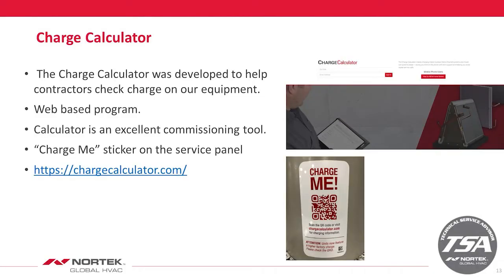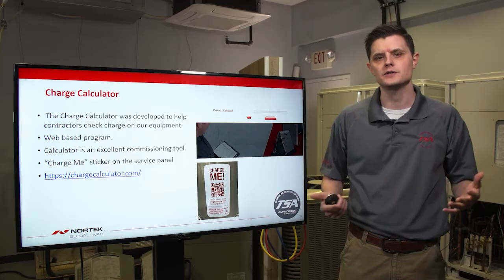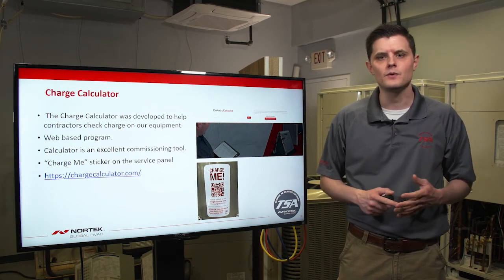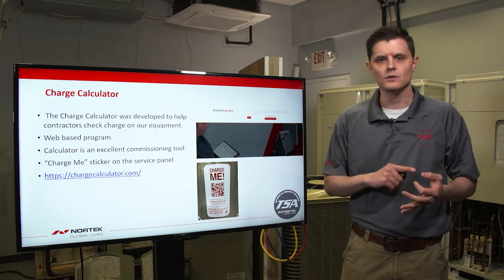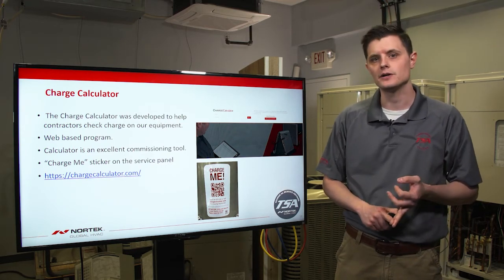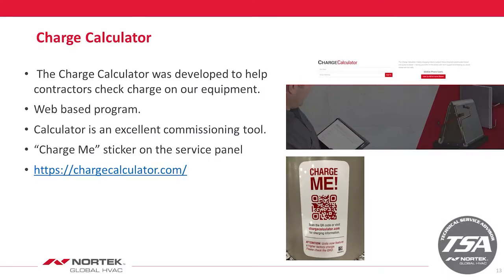Another tool is our charge calculator, developed to help contractors check charge on our equipment. It's a web-based program and an excellent commissioning tool for contractors in the field during a startup—helping determine whether they need to add or remove charge based on their install. You can access it two ways: via the 'Charge Me' QR sticker on the service panel of the equipment, or by going directly to chargecalculator.com.